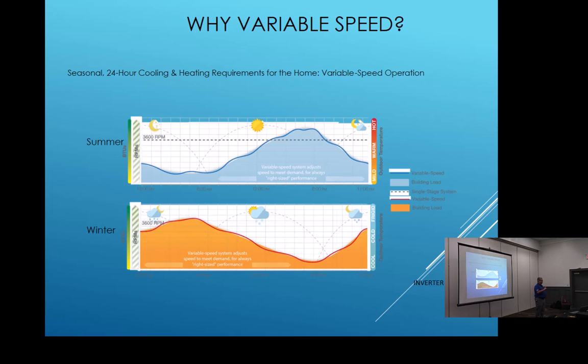Okay. And as we get up during the day, we go above that threshold of capacity for that fixed speed compressor at 3,600, and now we can go up past that and hopefully keep up with the demand during the day going forward, okay, and maintain that comfort level within 1 degree. Kind of a comparison here with our set point, our variable speed compressor. You can see how close that green line there goes to our set temperature within 1 degree.